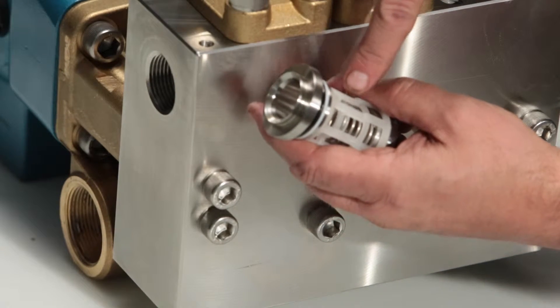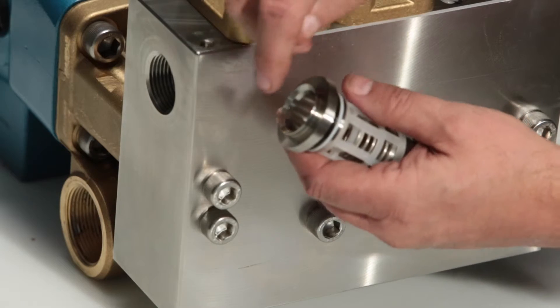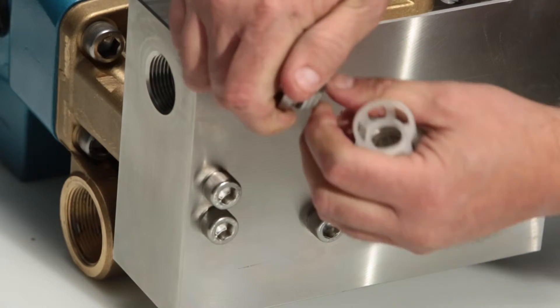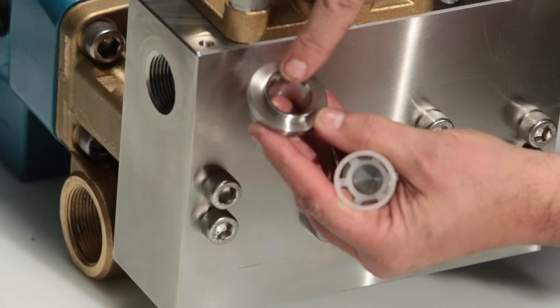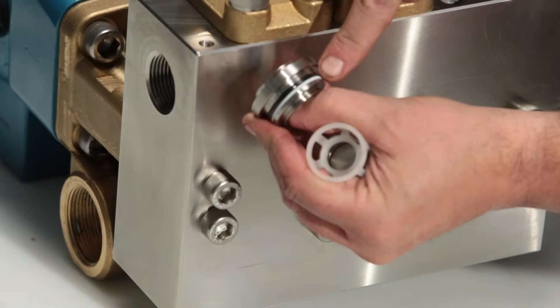To separate the valve seat from the inlet retainer, you can pull apart by hand. Inspect the discharge seat for pitting where the valve rests, as well as the o-ring and backup ring for any damage.